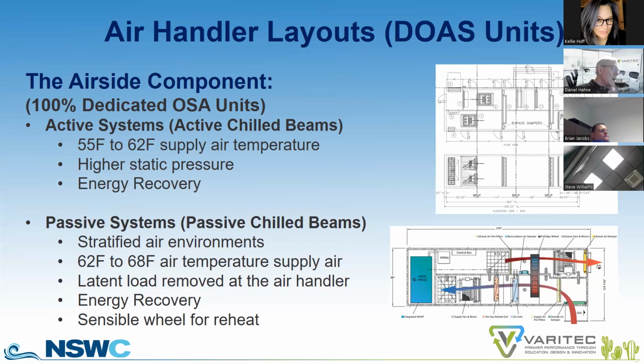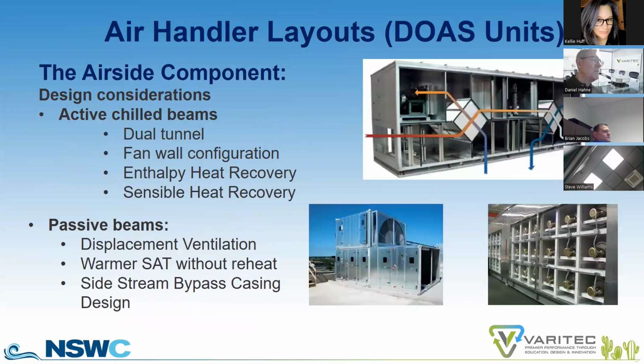But what's attractive about this is that if you can supply 65 degree air to a building versus 55 degree air, in Maricopa County, you can move from maybe 17% annualized hours operating in economizer mode and double that to maybe 34 to 35% of the annualized hours of a year in our dry, temperate climate months of between October, November through to March, April. So be aware of the difference in the DOAS configuration between a passive and an active chill beam system.